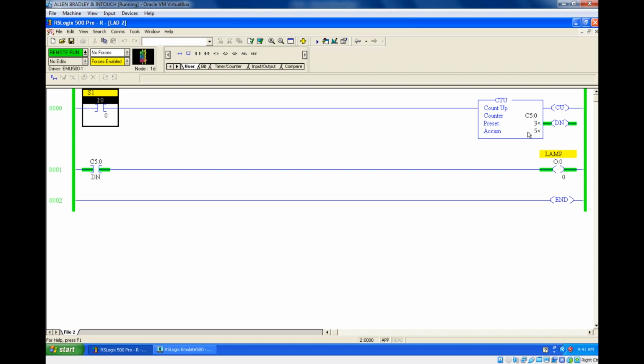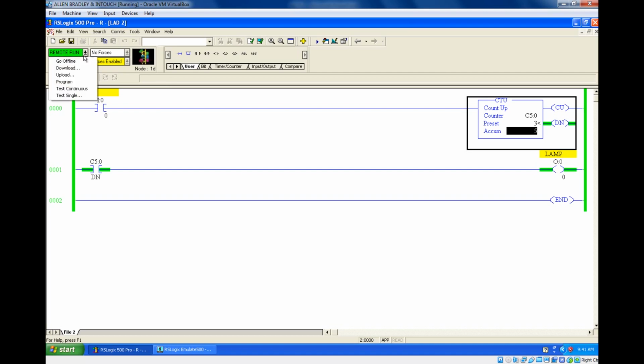Okay. So what is the accumulator limit? It will go up to 32767 and then roll back to -32768, because the counter limit is -32768 to +32767. So even though you keep giving pulses, it will keep counting, increasing up to 32767. After that, if you still give a pulse, it will roll back to -32768. Again it will start increasing from that place. I'll show you that.